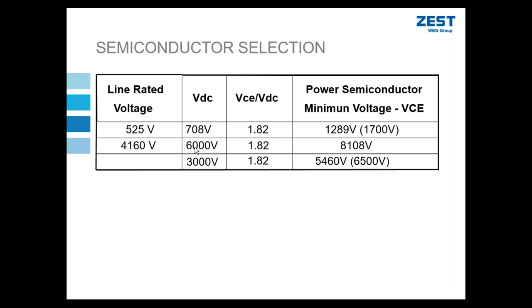But fortunately, our topology is not like a low voltage topology. We have the neutral point introduced like I showed you. And so our DC link voltage in the 4.16 kV case that any IGBT would be switching is limited to 3000 volts. If I apply my safety factor to that, it means my device would need to be rated as a minimum of 5.4 kV, but I use 6.5 kV devices.